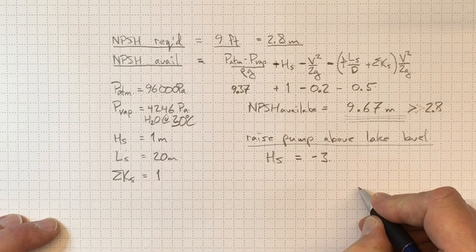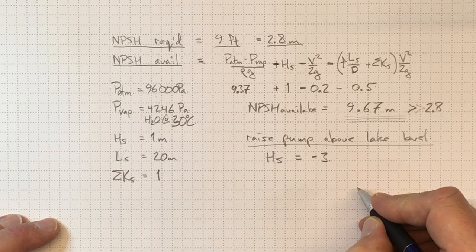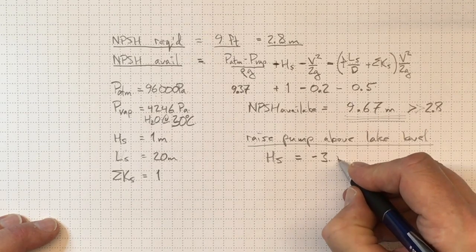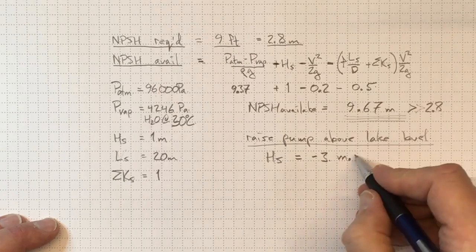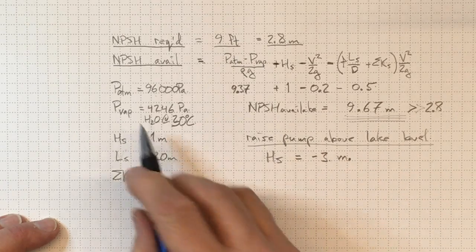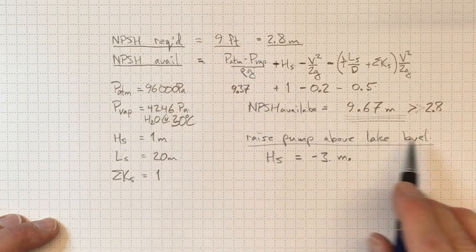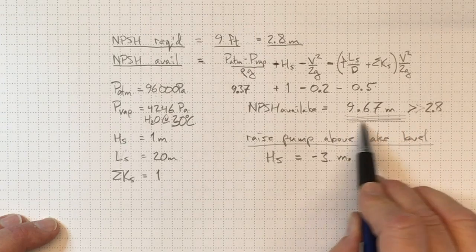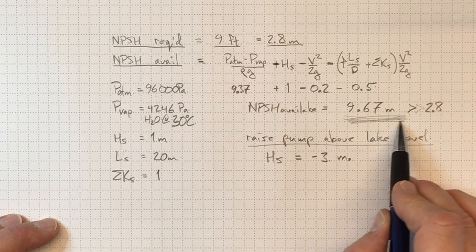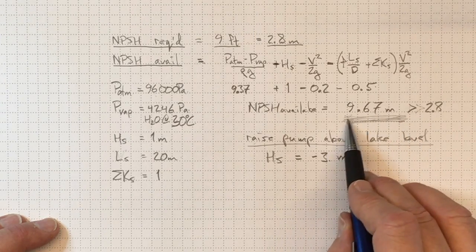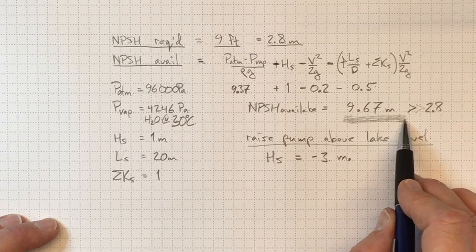We could be 3 meters above lake level, well up onto the shore. And that would be good from a practical design standpoint. So doing this NPSH calculation allows us to find out just how much space we have left in order to enable us to avoid cavitation.